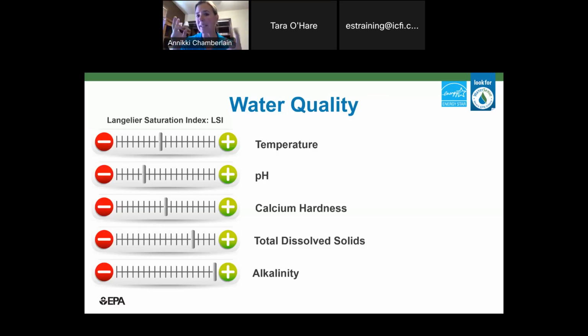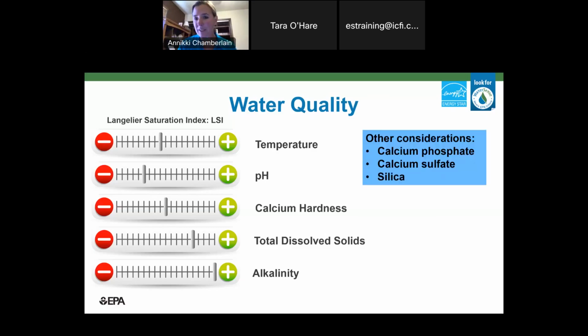The LSI is basically a model that will tell you if your water is more likely to corrode or to scale. Again, it's a bit theoretical, but very common. But there's also other considerations. You know, calcium carbonate is only one of the kind of impurities that could cause scale. Some places, like if you have silica in your water supply, you are in for a real treat. It's going to definitely limit your cycles of concentration, particularly once you get over about 150 parts per million, unless you have a higher pH.